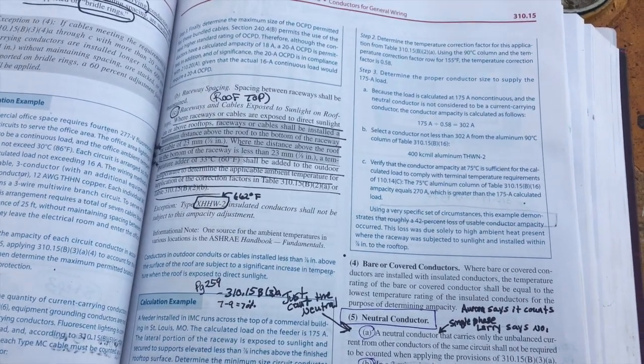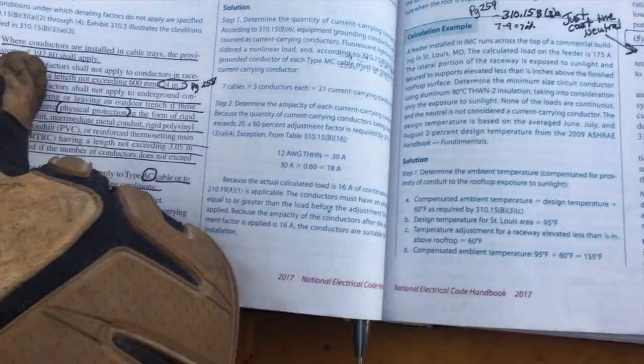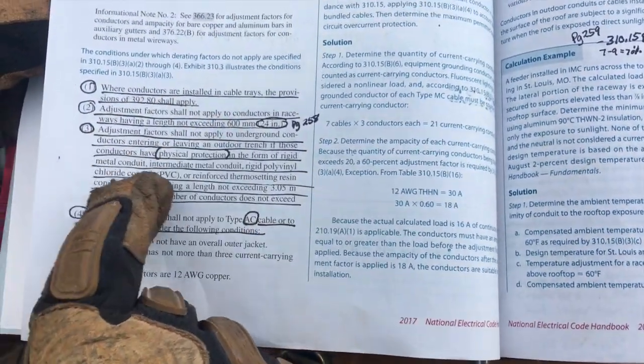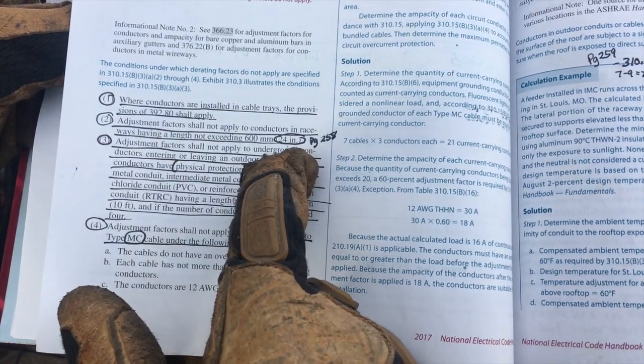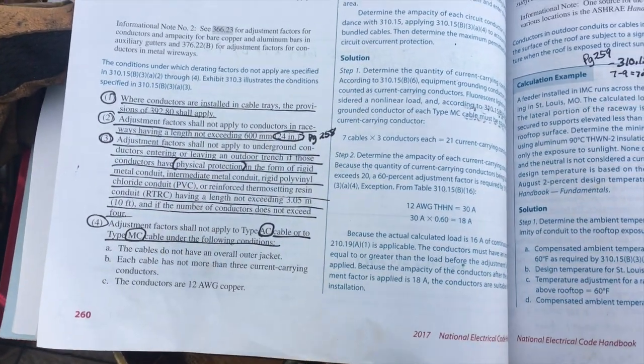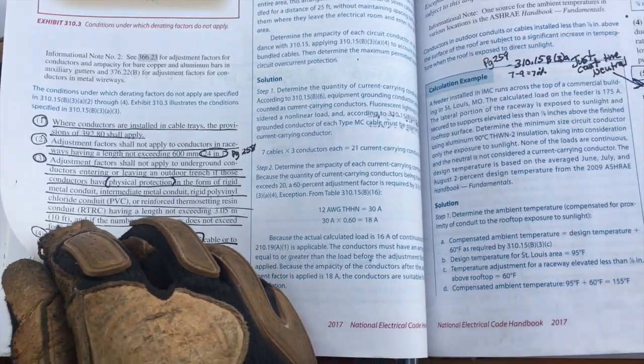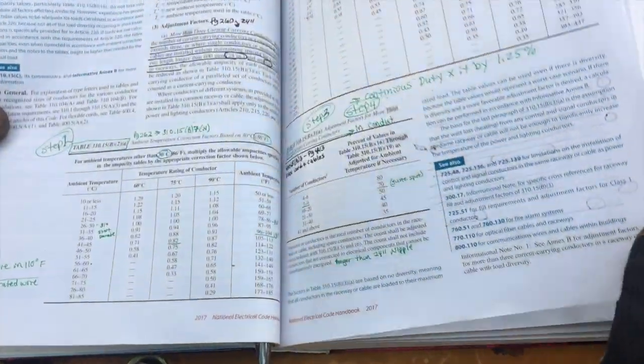You also have to look at when you're looking through this, where your conductors, if there's any adjustment factor if you're in a nipple. And in this case we were not, we were definitely using just a JSOOW cord, extra hard duty rated, so it does not have to be protected by a raceway.